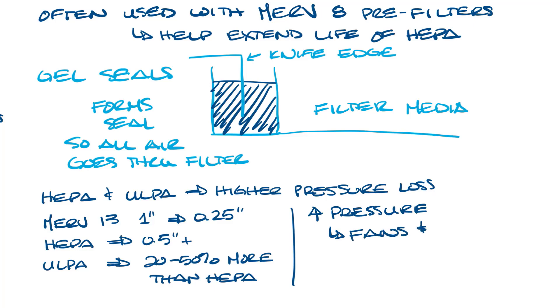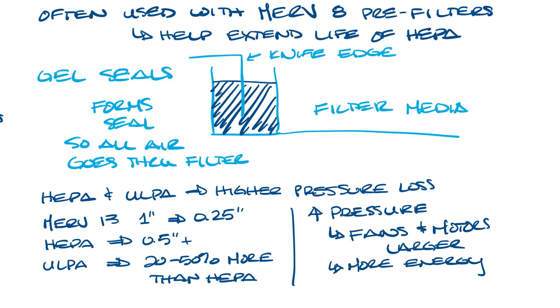Your fans and motors usually have to be larger to produce the airflow that you need, meaning it will also use more energy. For this reason, it's difficult to retrofit a system with HEPA or ULPA filters.